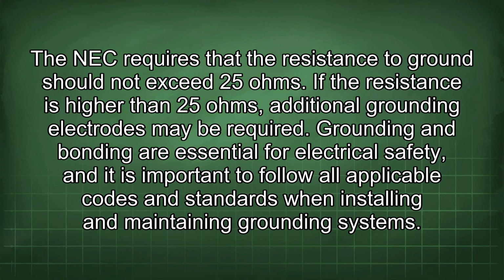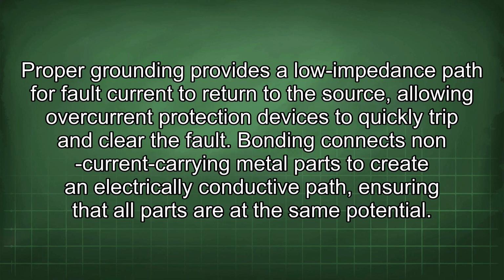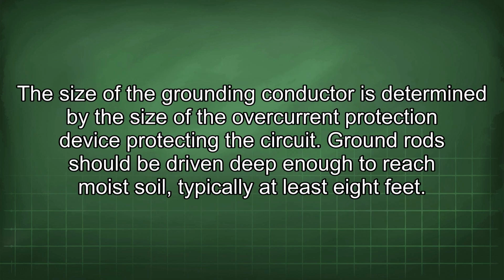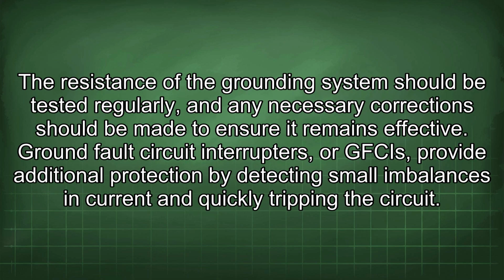Grounding and bonding are essential for electrical safety, and it is important to follow all applicable codes and standards when installing and maintaining grounding systems. Proper grounding provides a low impedance path for fault current to return to the source, allowing overcurrent protection devices to quickly trip and clear the fault. Bonding connects non-current carrying metal parts to create an electrically conductive path, ensuring that all parts are at the same potential. The size of the grounding conductor is determined by the size of the overcurrent protection device protecting the circuit. Ground rods should be driven deep enough to reach moist soil, typically at least 8 feet. The resistance of the grounding system should be tested regularly, and any necessary corrections should be made to ensure it remains effective.